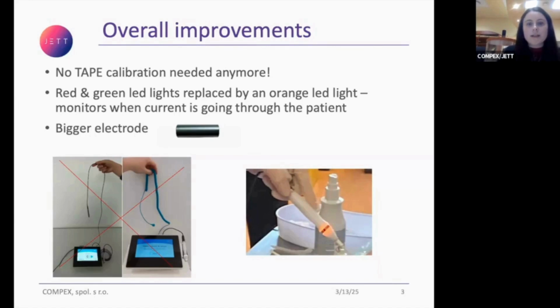Additionally, as a lot of you know, previously a red light lit up on the plasma pen when there wasn't any current going through to the patient, and it switched to a green light once current started going through. And this has been replaced now by an orange light. So instead of the red light previously, no light will be lit on the pen before contact. And then when the plasma pen tip is at 2 millimeters or less from the patient's skin, current starts going through, and therefore at the same time the orange light will show. This is mostly to prevent possible interventions with the device and operational errors. You can see the orange light there on the second picture.